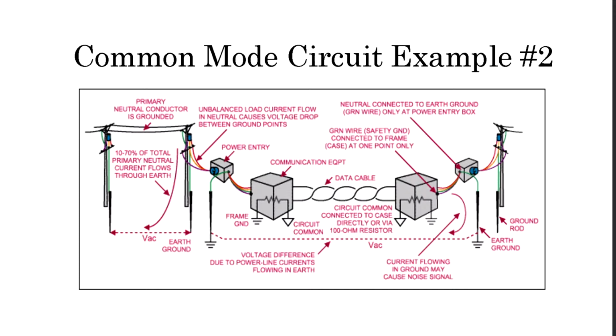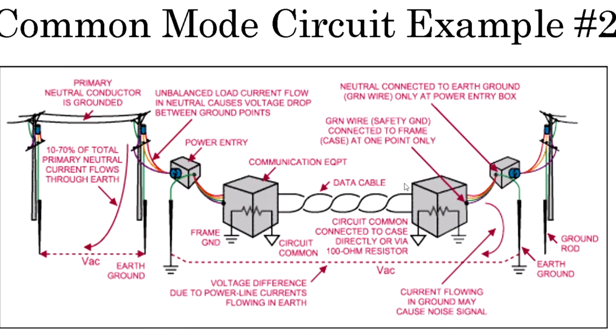demonstrate common mode noises. Showing everything kind of compounded together and how it all adds up. Over here on the left, you see we've got the utility, and they're basically showing you how the utility is able to inject current into their ground system, into the earth, because at every pole they have what's called a multi-grounded neutral. At every pole, they've got a ground conductor, the pole ground, coming up to the top, and it's bonded to the neutral. That's in parallel. That puts earth in parallel. And as they state here, most of the current on the neutral is actually flowing through earth.